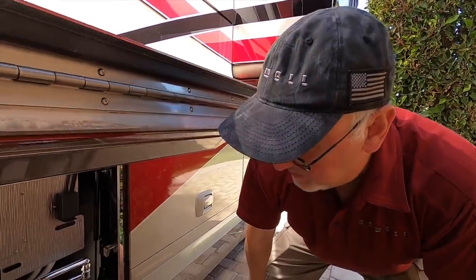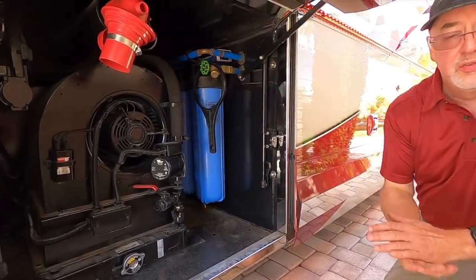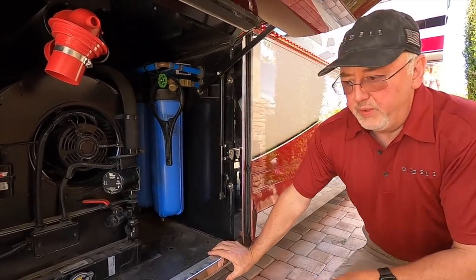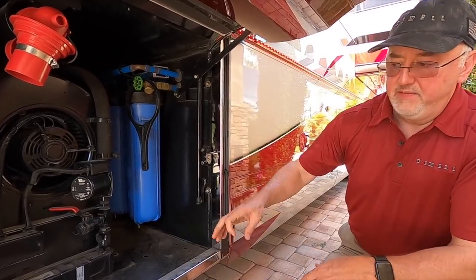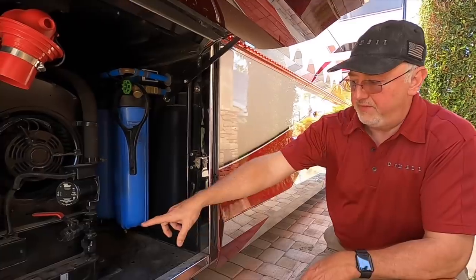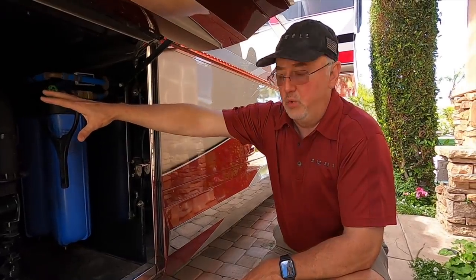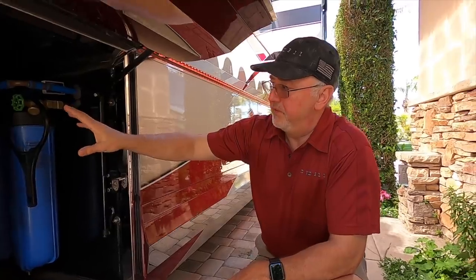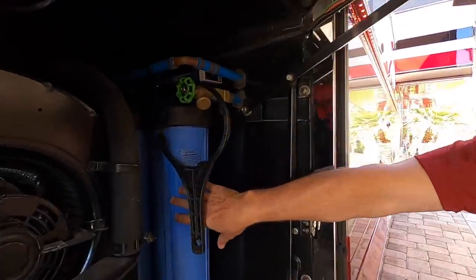In this bay you'll notice that on some generators in the industry there'll be a small radiator on the side of the generator. But we want far better cooling than that. We have a 20kW diesel generator, and instead of one of those small radiators, we've got a large radiator with a huge cooling system that takes air through the bay door and down below. There's also ventilation from the electrical bay that comes over to this side. And here are the DI water filters.